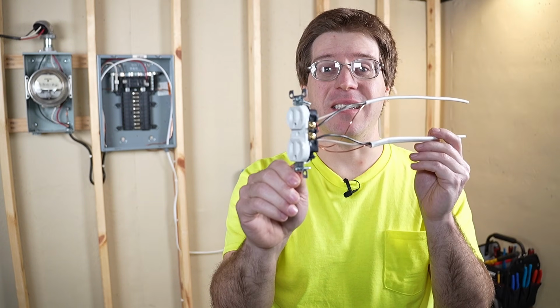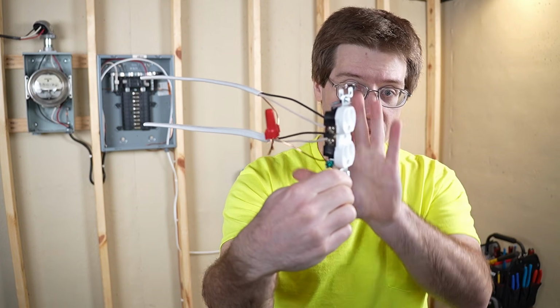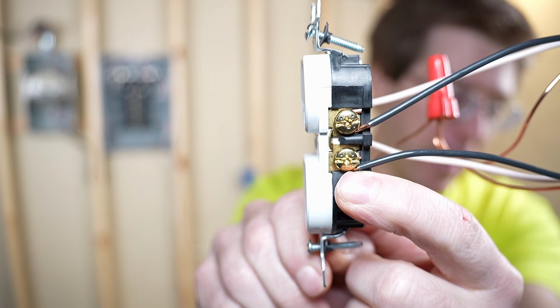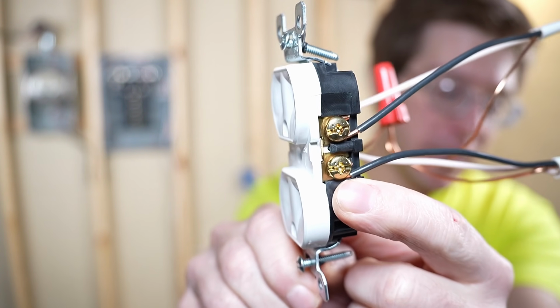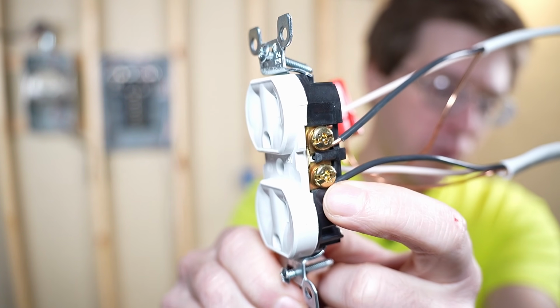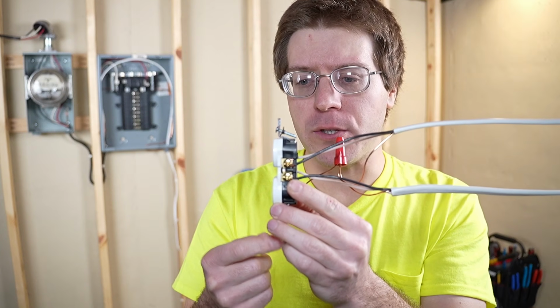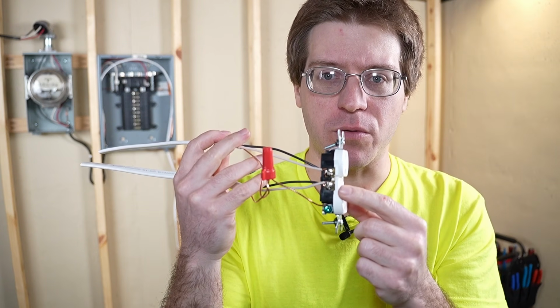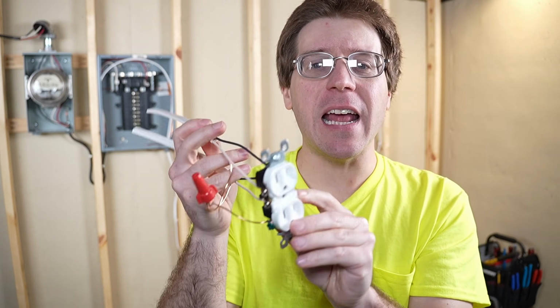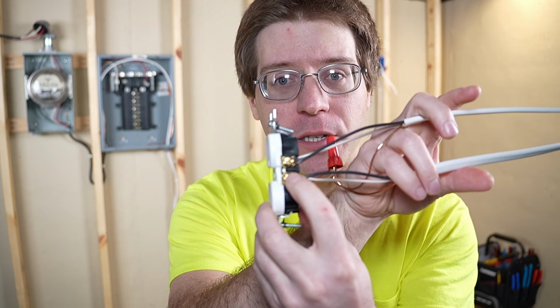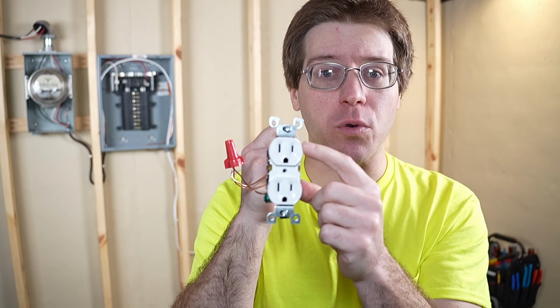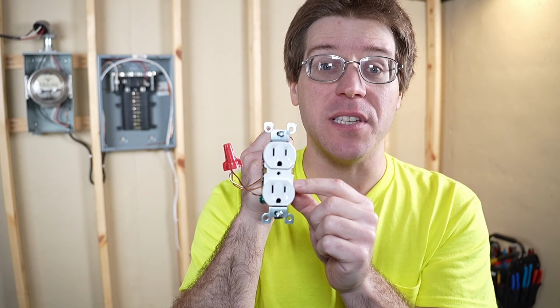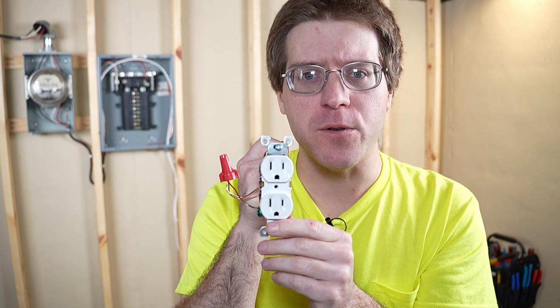So while it is not against code to do this, this is perfectly acceptable per code, and a lot of people actually argue that that is the reason for having multiple screws on a receptacle. And while that might be true, my understanding is the main purpose for having the multiple sets of screws is so we can break the tab between the 2 sets, and control these individual receptacles individually. That'll be a topic for a future video.